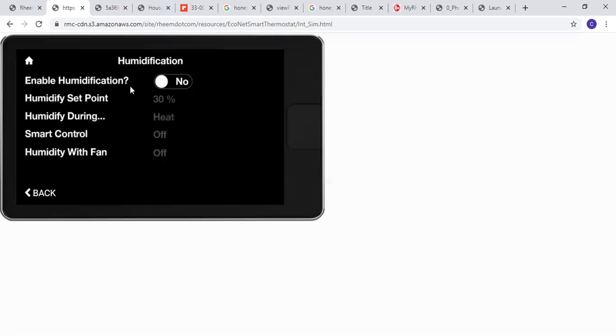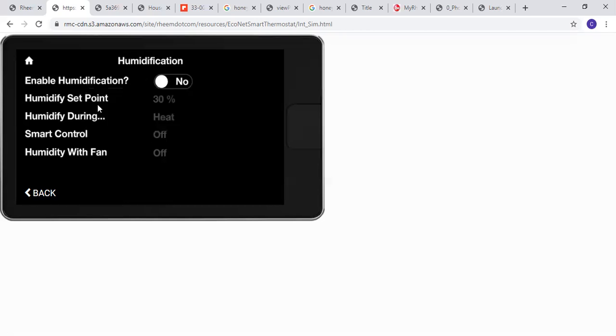So we can set up our humidification. We can enable it here. We can set our humidity set point. We can humidify during heat, even cool if you wanted to, and heat and fan. You can set up your smart control. And then you can also say humidify with fan. And down here you can pick your actual speeds. I want low speed with humidification, medium, whatever speed that you'd like.